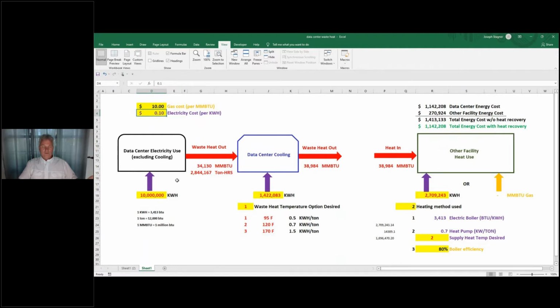But this diagram shows, for example, suppose we have a data center on the left side here, and we're using 10 million kilowatt hours for computing and everything else in the PUE except cooling. All that electricity for lighting and computing turns to heat after it's done its work. It's no place else for it to go. It all turns to heat. So if you put 10 million kilowatt hours of electricity into a building, you're going to generate 34,000 million BTUs of heat, because 1 kilowatt hour equals 3,413 BTUs when converted to heat.